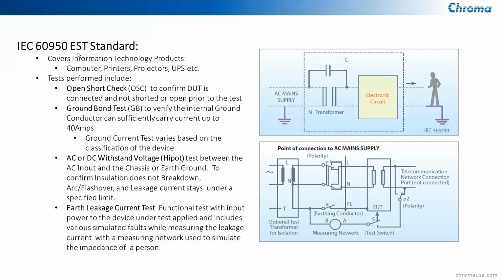So the IEC 60950 standard also includes requirements for ground bond, and it also includes requirements for high voltage withstand and earth leakage current testing. Within this standard, which is for information technology products like computers, printers, projectors, etc., it also has the leakage current test, which uses a certain type of measuring network to simulate the impedance of the patient or the operator or anybody that would come in contact with the equipment.